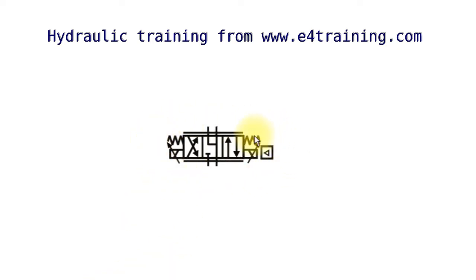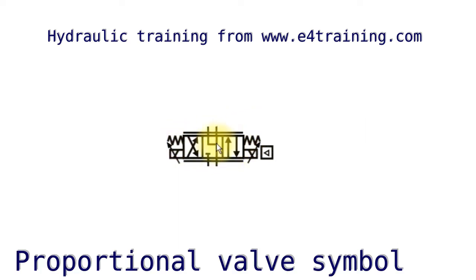They're both identified by this symbol. The difference between a directional valve symbol - the internals are the same here - are these two lines which indicate the valve is proportional. So rather than opening from one side to the other, it opens gradually, giving different flow depending on the position it's at. We may see as well the arrow across the solenoid, which shows it's a proportional solenoid, moving gradually rather than just from one side to the other.